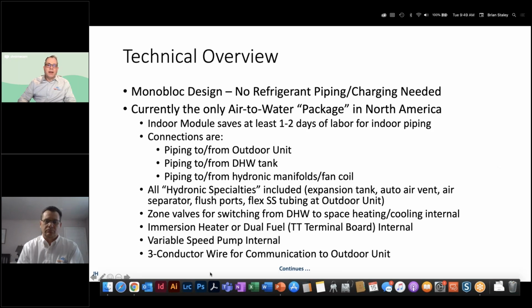The zone valves are inside that indoor module as well. That's a pretty big deal from a labor and piping standpoint. If we want to do domestic hot water, those zone valves switch from the hydronic heating or cooling over to the tank and back. So we're not messing with three-way valves, lots of piping.